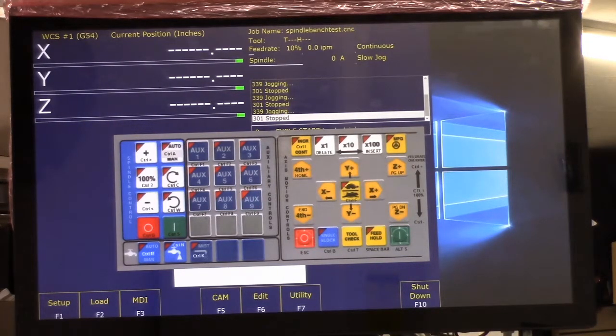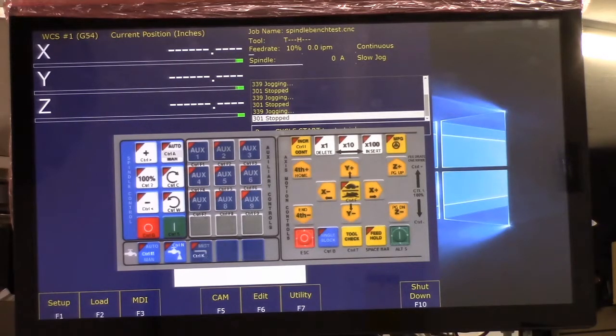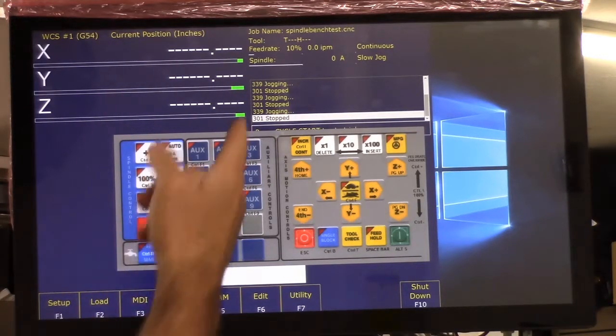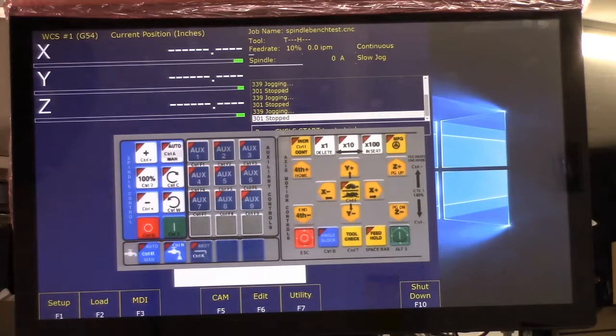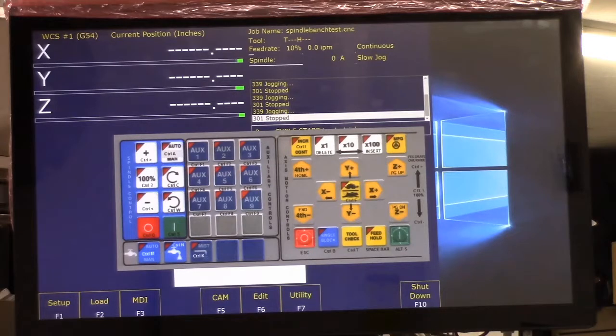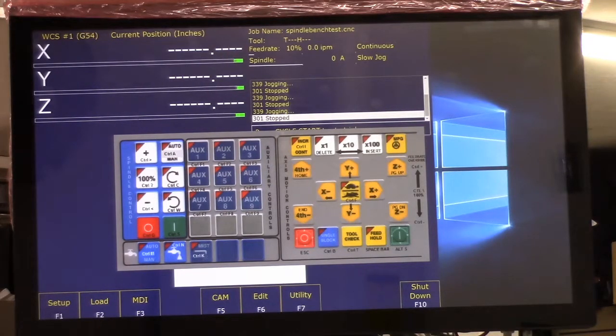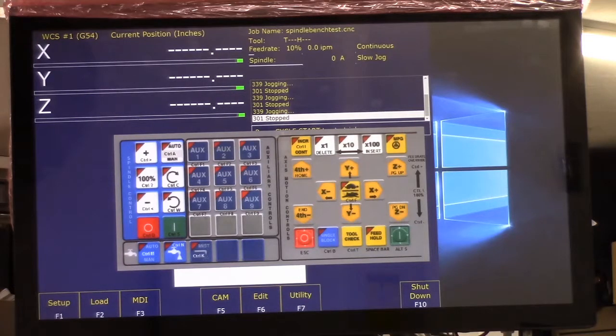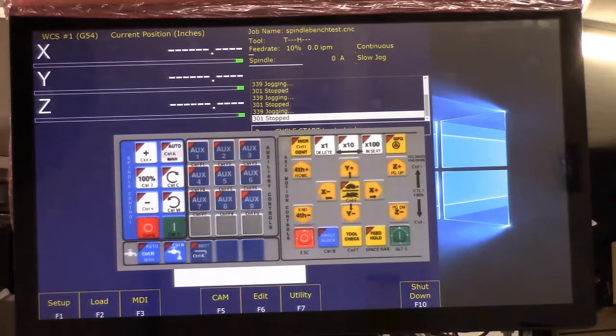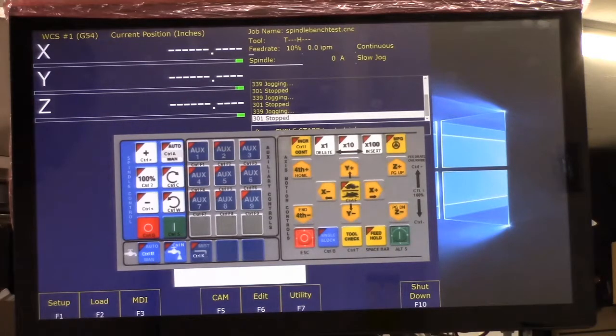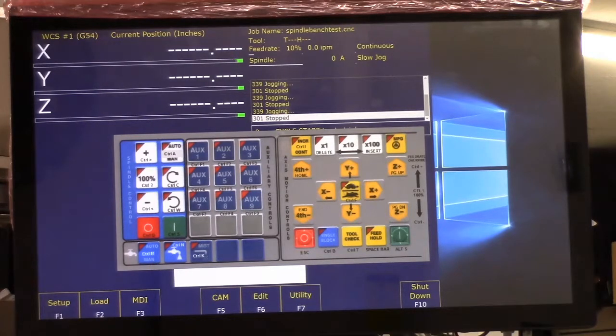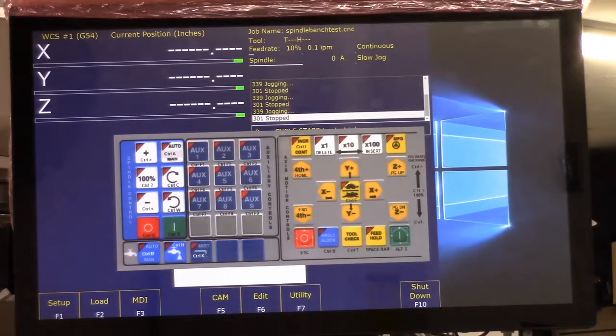Troubleshooting tip number one: if movement does not occur, check for errors in the status window. We don't have any errors. And then the next tip, number two: if during jogging or while holding position the motors are visibly oscillating, there is most likely a problem with your PID settings. Manually tune the motor using tech bulletin 260, which can be found here, and it gives you a link to that tech bulletin.